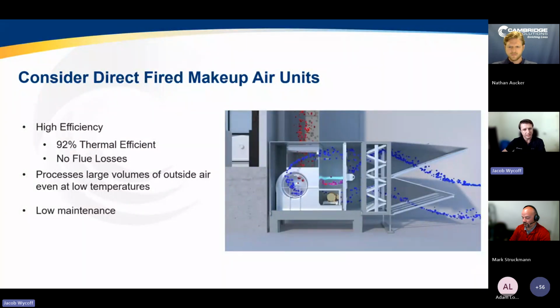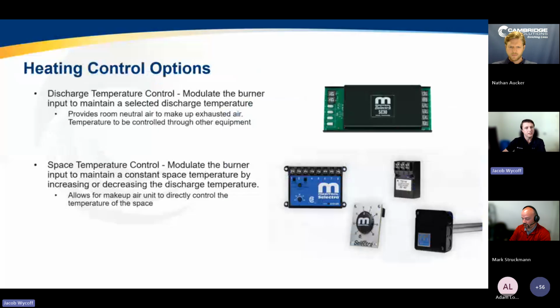So like I said, your manufacturing facilities are going to vary pretty greatly from building to building, so it's tough to give too much specific advice. But these are just some general things that you want to be thinking about early when you're going about these industrial retrofit opportunities. So number one, how are you going to control the heat of that makeup air unit? Do you want to control the discharge temperature, where you're modulating the burner to be able to maintain a specific discharge temperature? In most of these cases, you're going to be providing room neutral air to make up any exhausted air that's happening inside the facility.